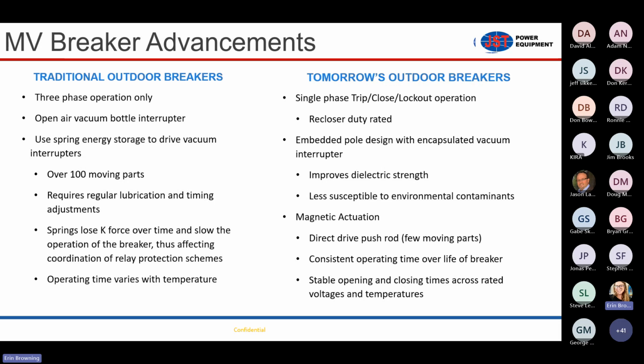You don't get any sag, in other words, as the breaker reaches 10,000 operations. And whether it's really cold outside or really hot outside, there's no springs that are going to be subjected to those temperature swings. So really, this actuator is operating off of a digital input into a controller and a rapid application of voltage from a capacitor that is independent of temperatures. So we tested this breaker to high and low temperatures and have found that the operating speed changes, I think within microseconds, actually, very, very unaffected by temperature swings.